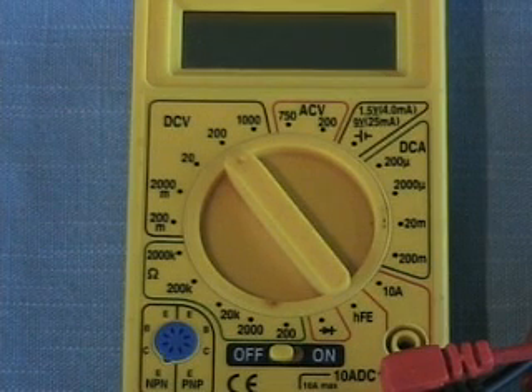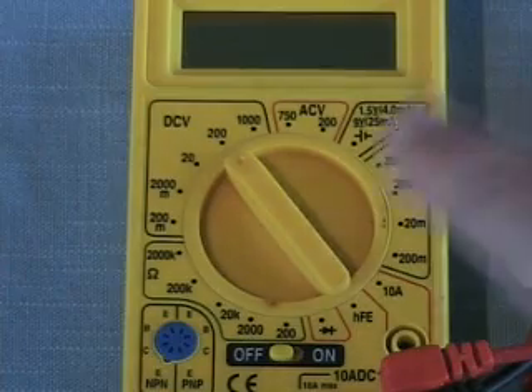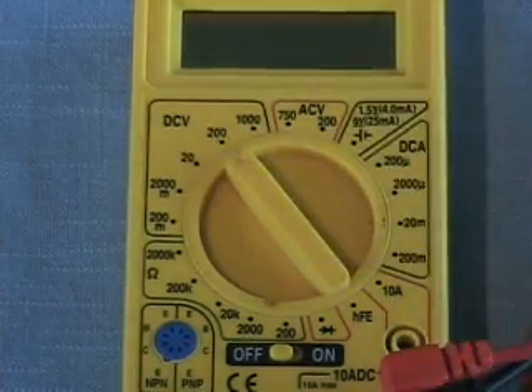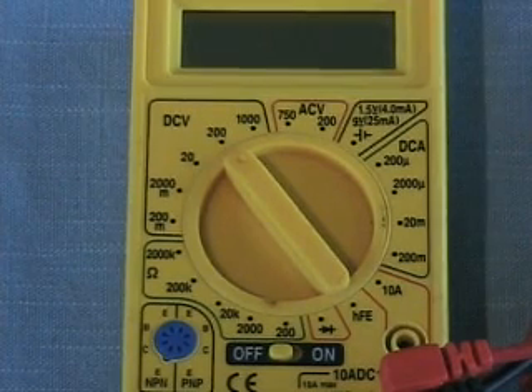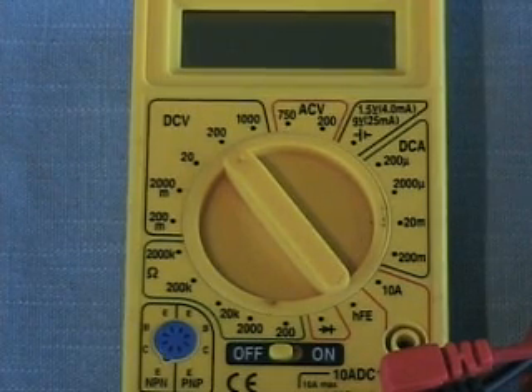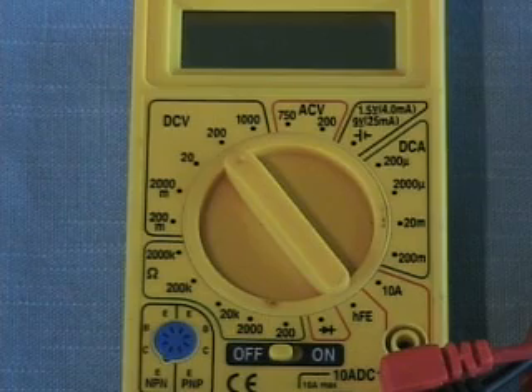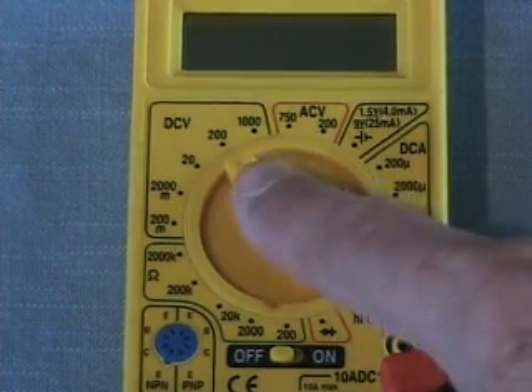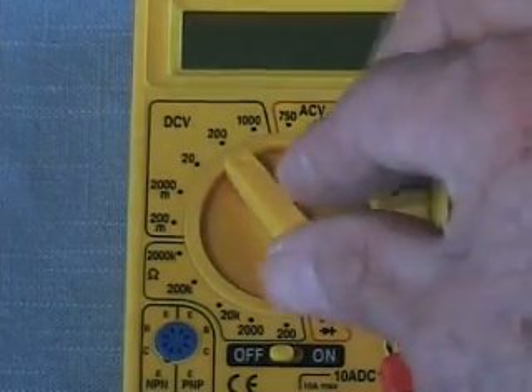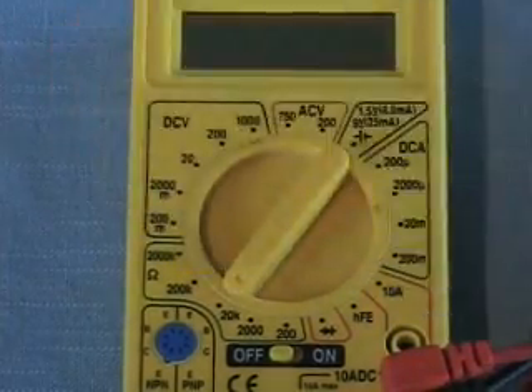Always make sure when you're testing DC volts on the transformer that the voltmeter is set higher than the output of the transformer. So for example, if the transformer is putting out 29 volts and you have it set on 20, you will not get an accurate reading. In this case, we have set the DC voltmeter to 200 volts. We will set the ohm meter to 200K.